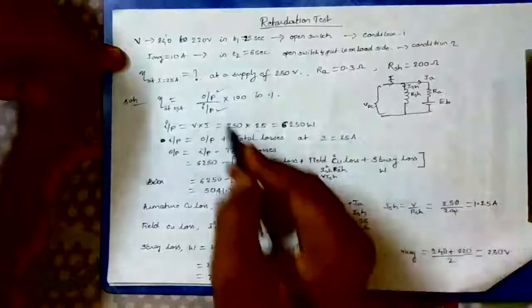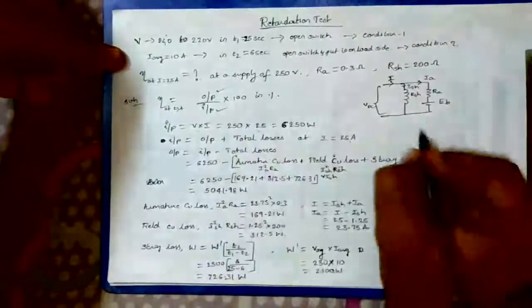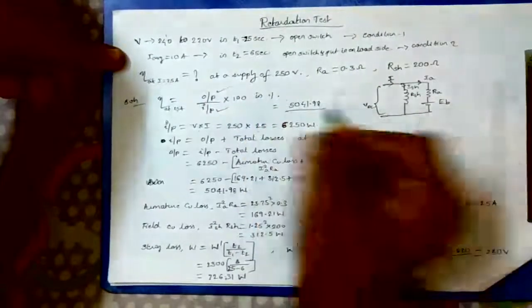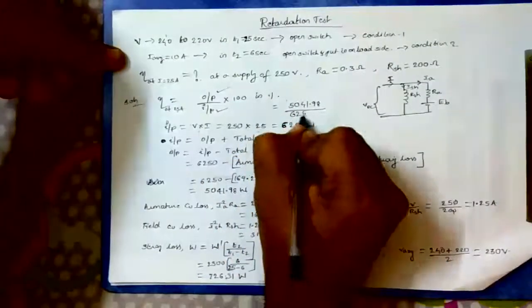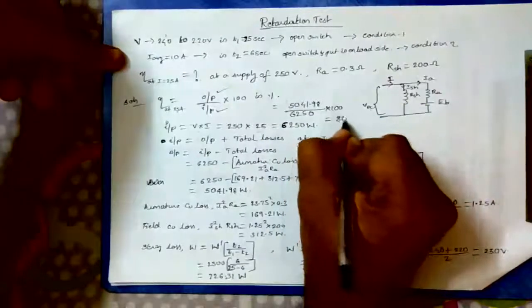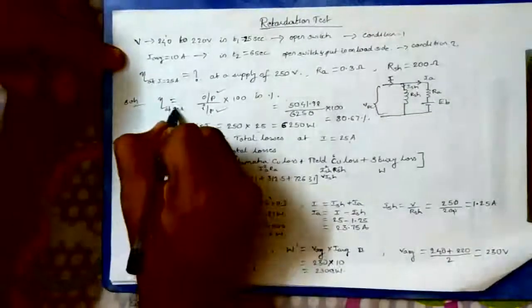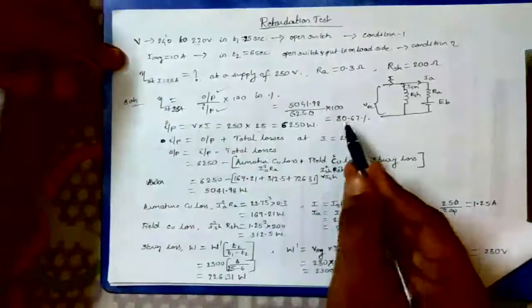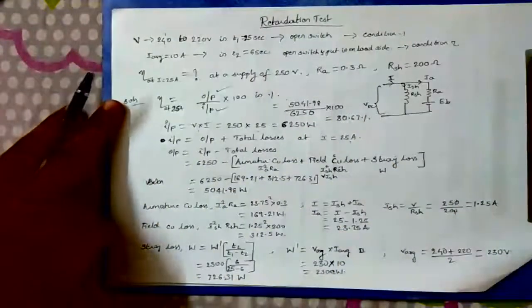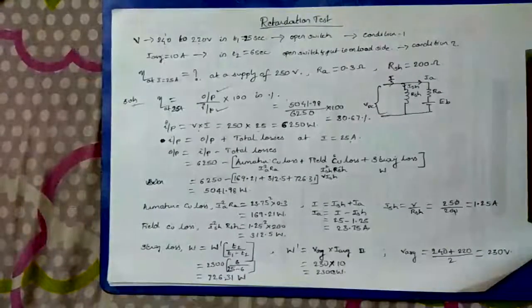Now I got output. Input we have calculated earlier. Just substitute output as well as input, multiply by 100, you will get the answer. Output is 5041.98 divided by input 6250 into 100. If I do calculation, I would be getting 80.67 percentile. That is efficiency of motor while delivering 25 ampere. This is how we calculate in retardation test. This is just a problem where we have calculated the efficiency of the motor when delivering 25 amperes.